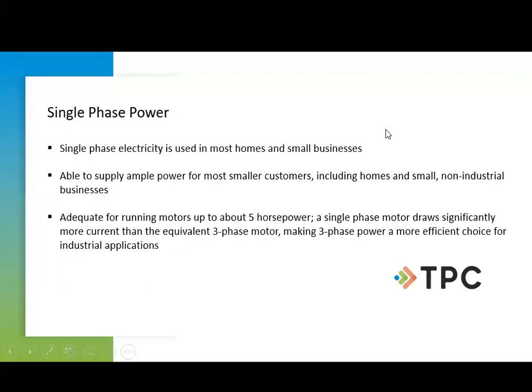And like I said, mostly residential or small business, and not used in industrial applications very often, but it is adequate to run up to a 5 horsepower motor. But here's what we have to remember about single phase: it does draw more current than an equivalent three-phase motor would. And so that means we're going to have larger size equipment, larger size conductors, and not as efficient. So if we could get three-phase to come into a facility or generate it ourselves, then that would definitely be a big advantage for us.